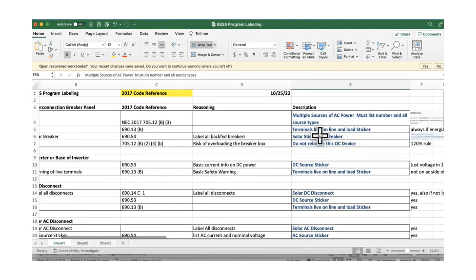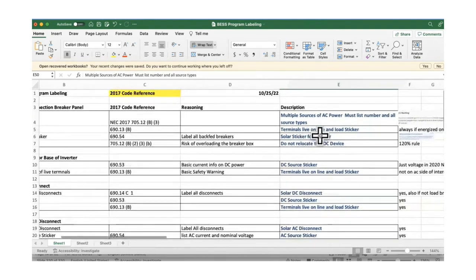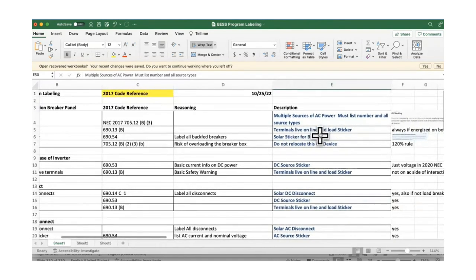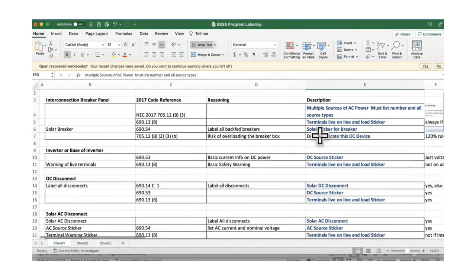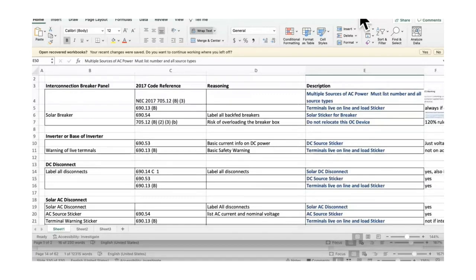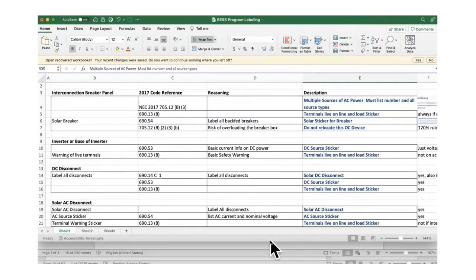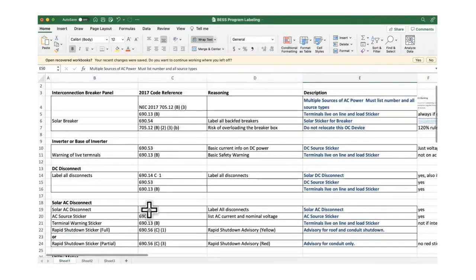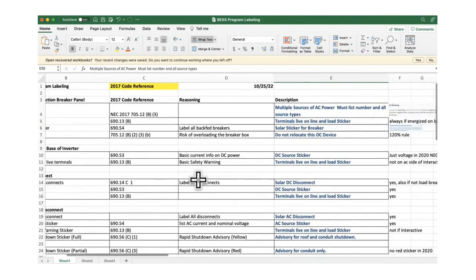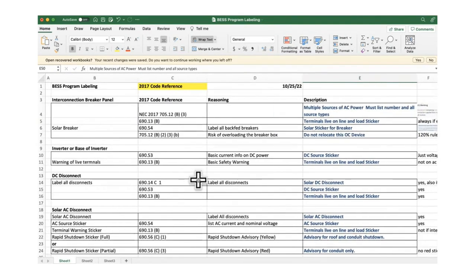Sure. My reasoning is if you install it on a PV system or a battery backup system, because it's a solar system, you have to say what it is. So if it's an AC disconnect, it has to say solar AC disconnect. If it's a battery stack, it has to say this is a battery storage stack, etc. I don't see that in the code anywhere. I just think that's just the way it is.